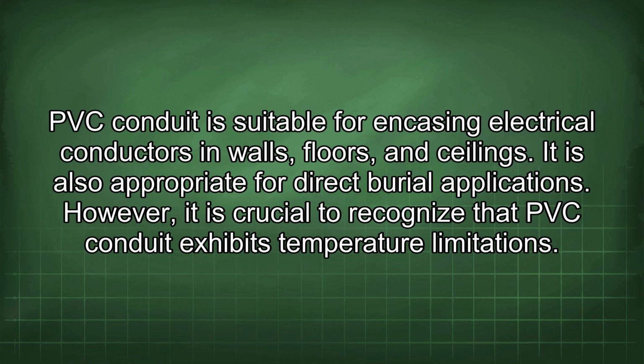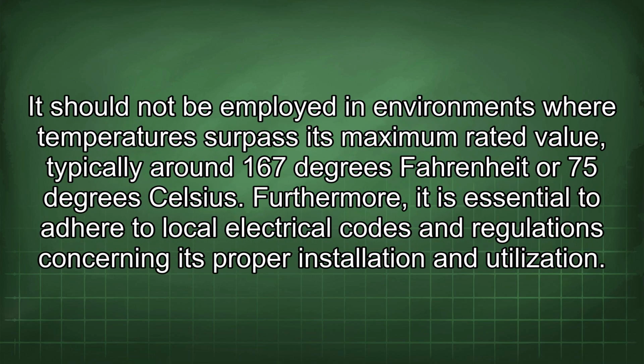However, it is crucial to recognize that PVC conduit exhibits temperature limitations. It should not be employed in environments where temperatures surpass its maximum rated value, typically around 167 degrees Fahrenheit or 75 degrees Celsius. Furthermore, it is essential to adhere to local electrical codes and regulations concerning its proper installation and utilization.